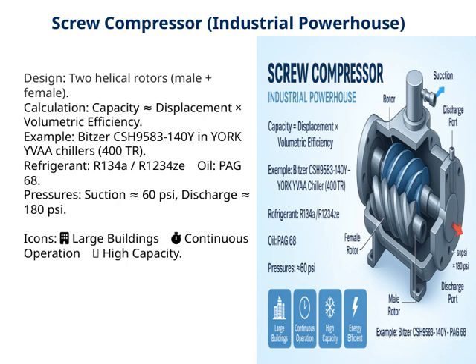For example, a common model like the Bitzer CSH9583-140Y is used in York YVAA chillers with around 400 tons of refrigeration. As for the refrigerants, these compressors typically run on R134a or R1234ze, with PAG 68 oil to keep everything lubricated smoothly. The operating pressures are also important. Suction pressure is usually around 60 psi, while discharge pressure can reach about 180 psi.